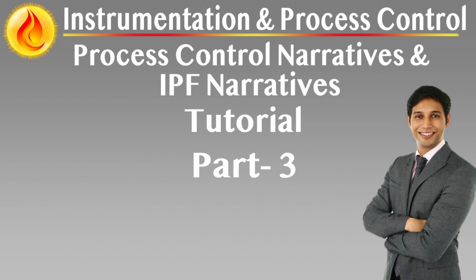Definition of the safe state. Each IPF must clearly define the safe state it is designed to achieve. This is the condition of the process or equipment after successful IPF activation, such as isolated flow via closed valves, depressurized vessel or system, rundown stopped or bypass initiated, fuel or heat source shutdown. The safe state description must reflect both the process objective and the physical end condition that ensures hazard mitigation.